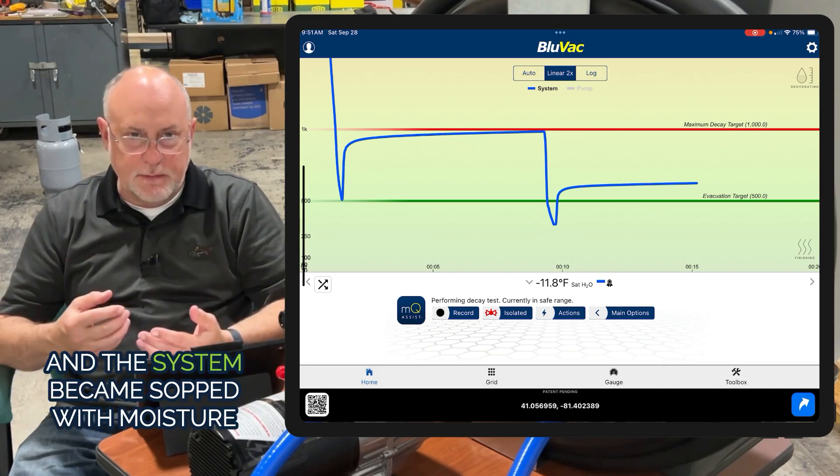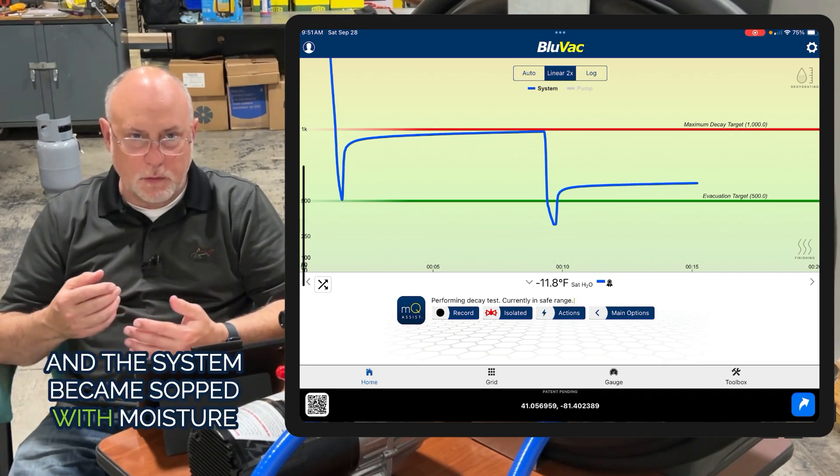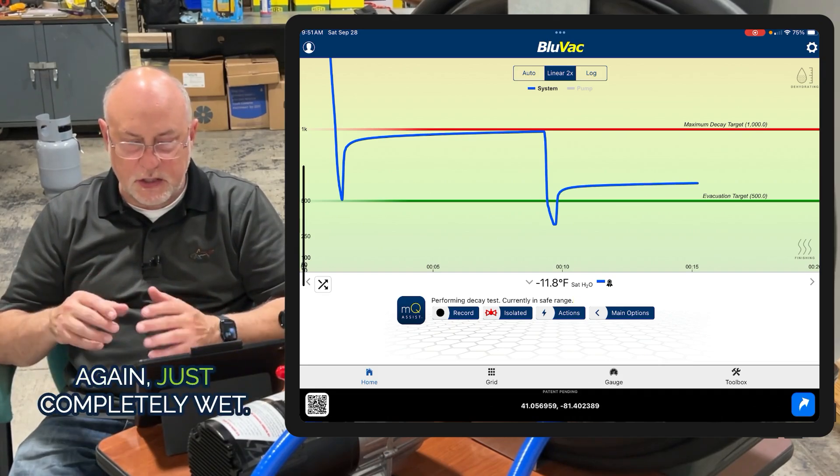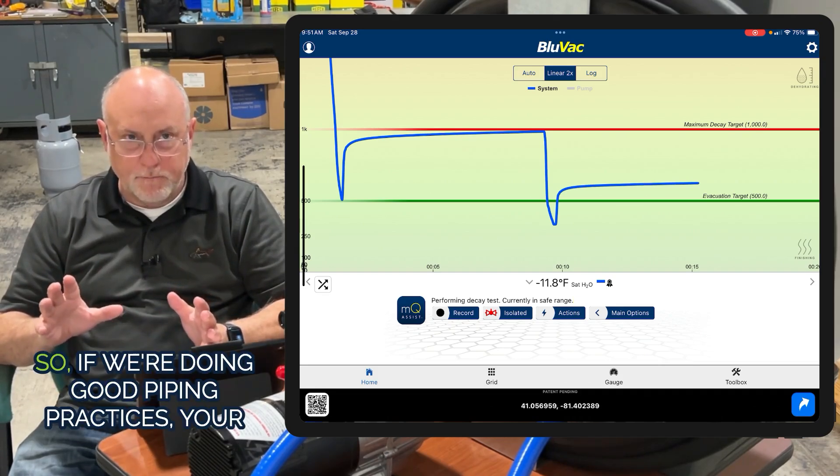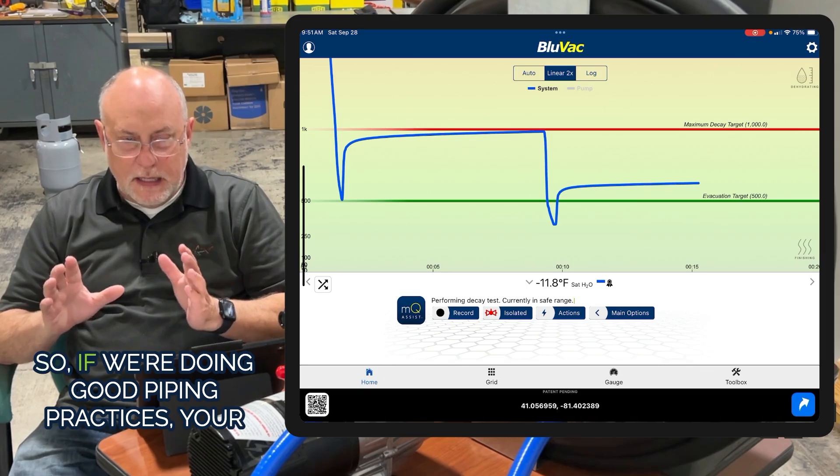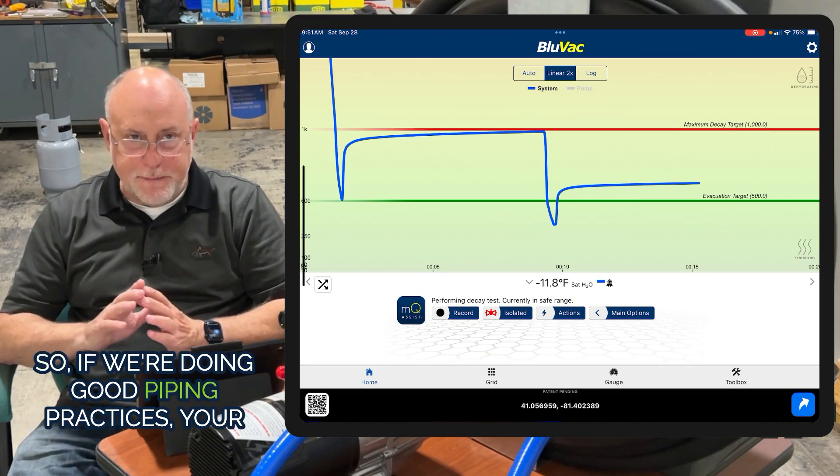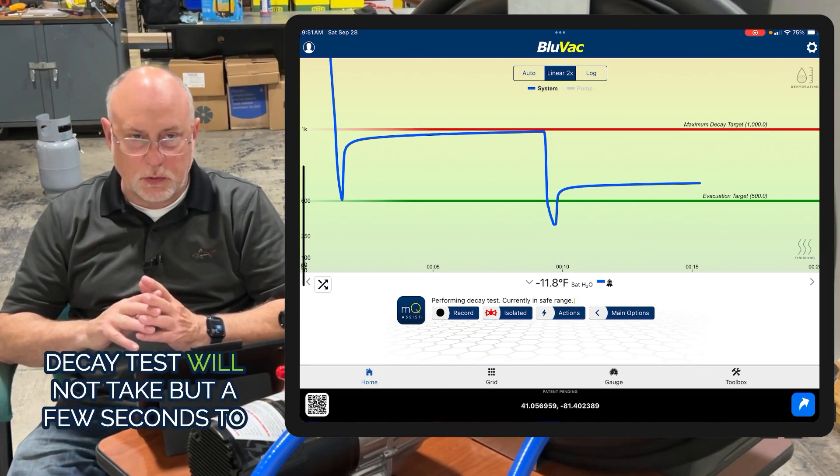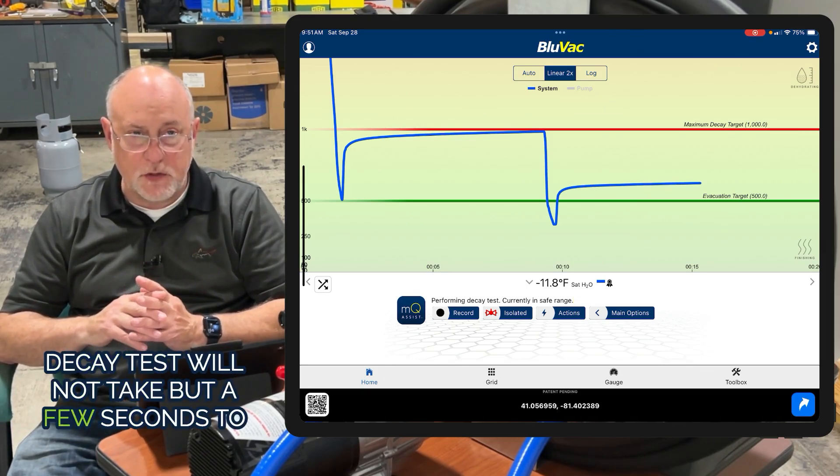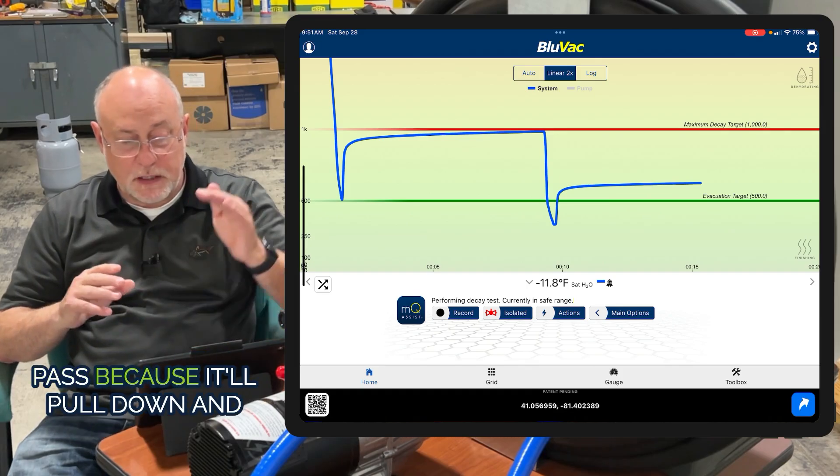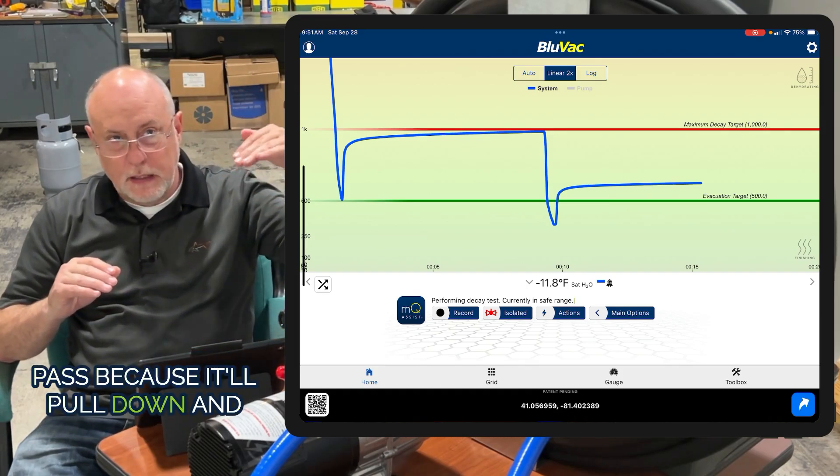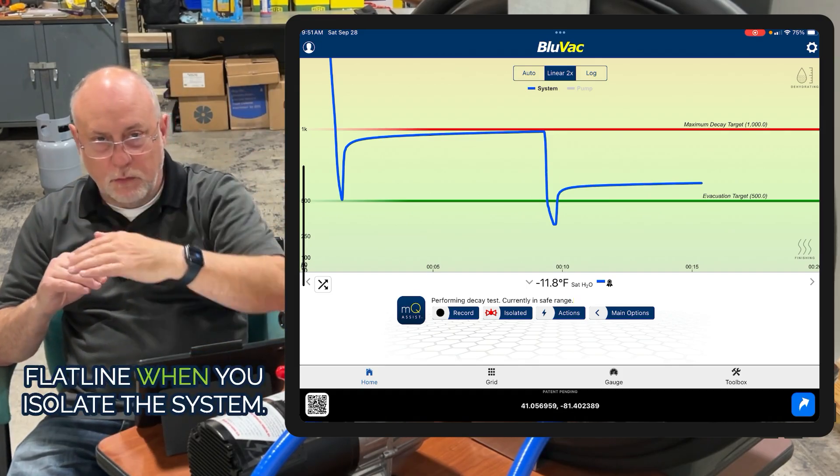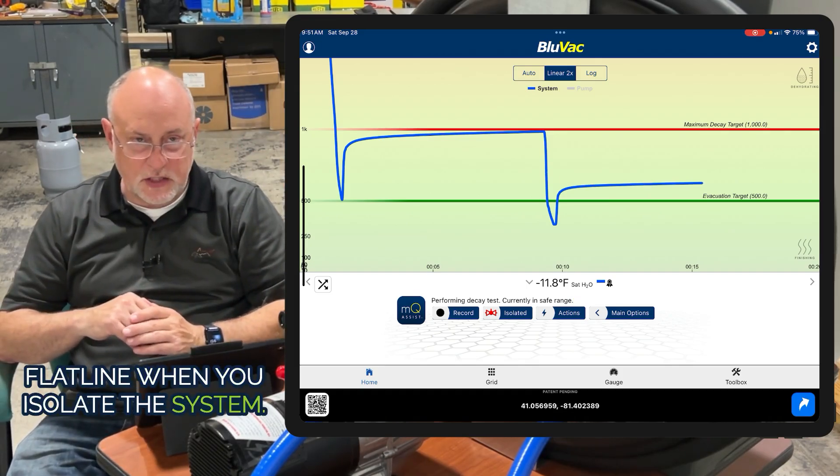We pulled atmospheric air in and the system became sopped with moisture again, just completely wet. If we're doing good piping practices, your decay tests will not take but a few seconds to pass because it'll pull down and flatline when you isolate the system.